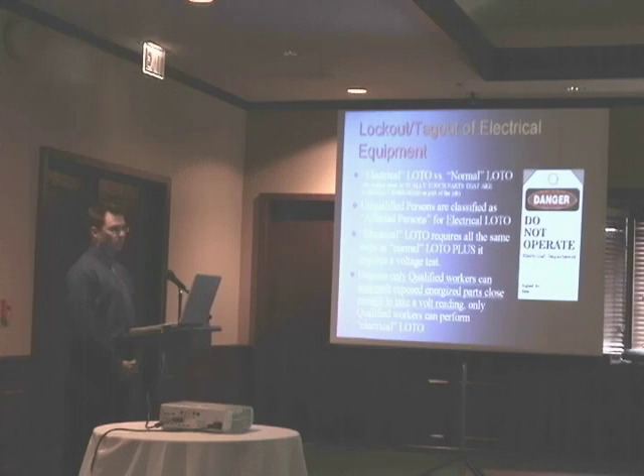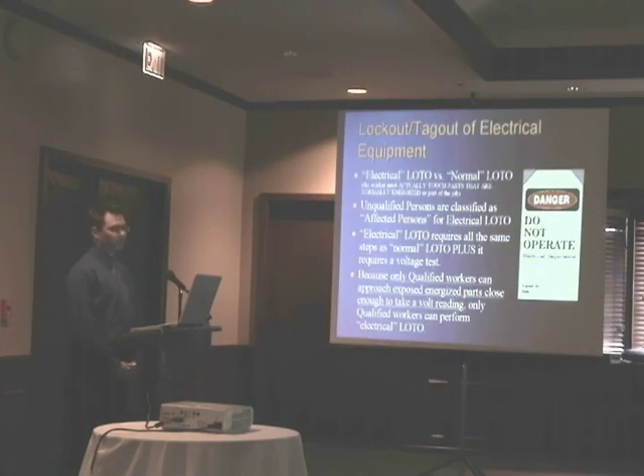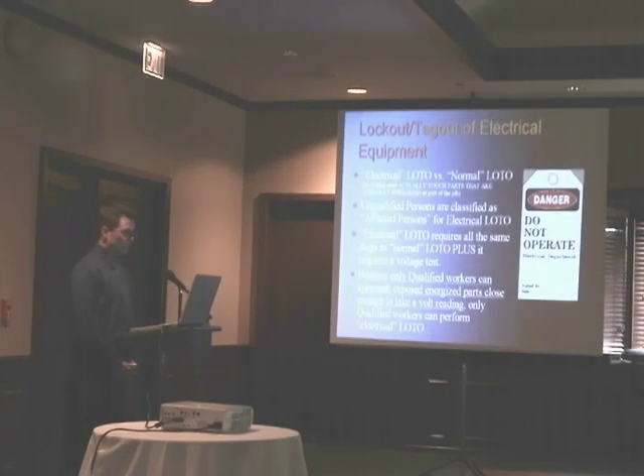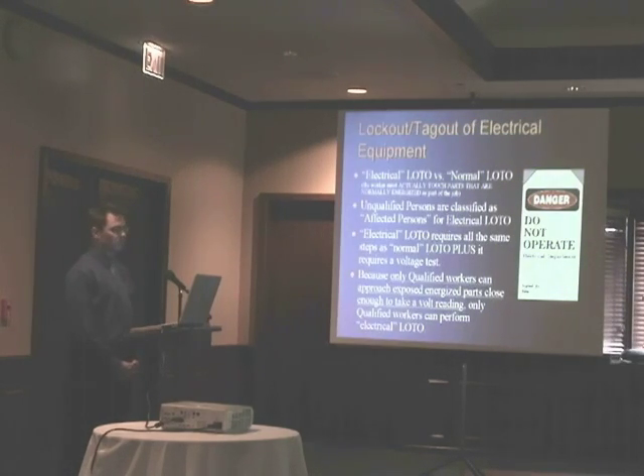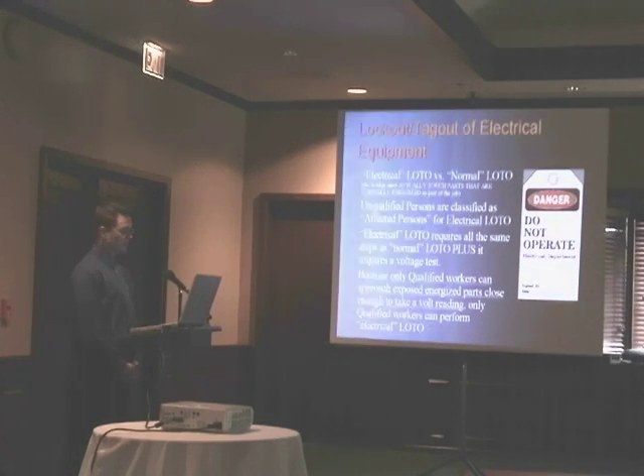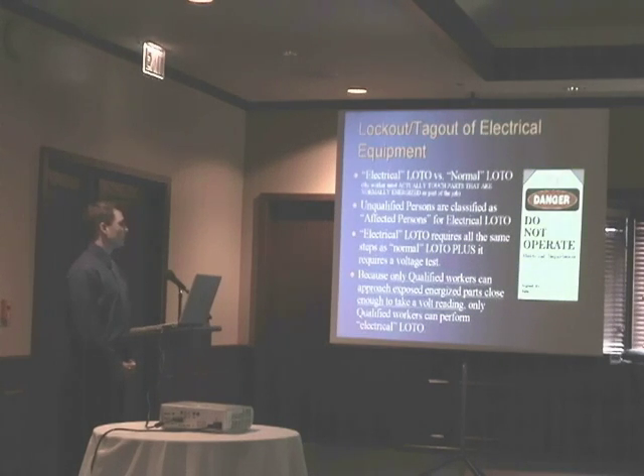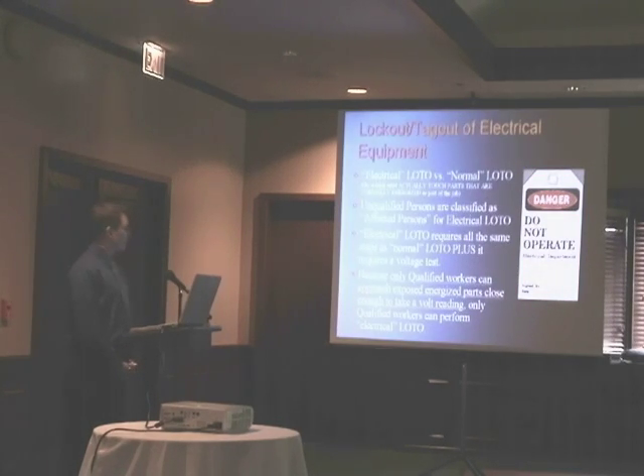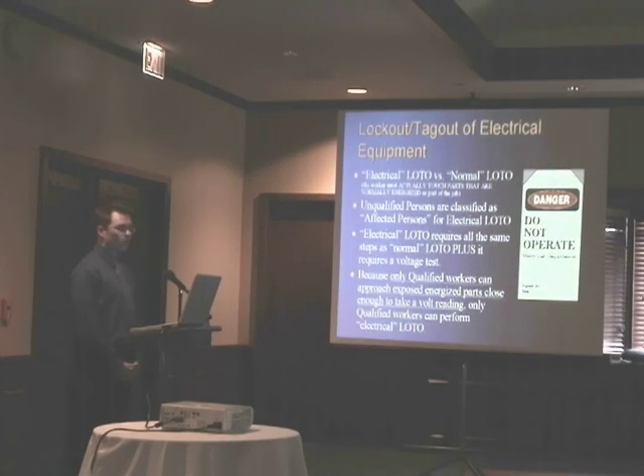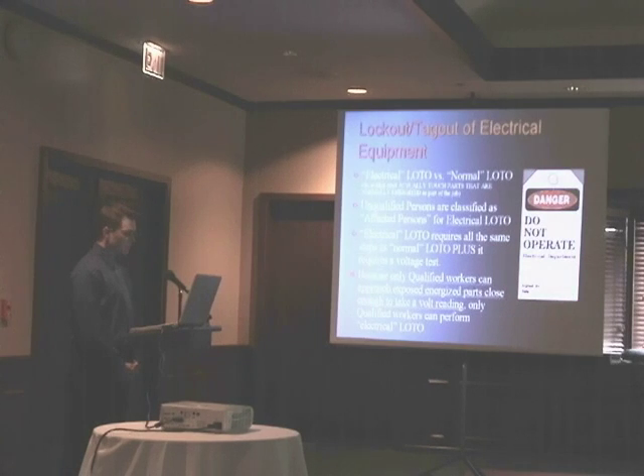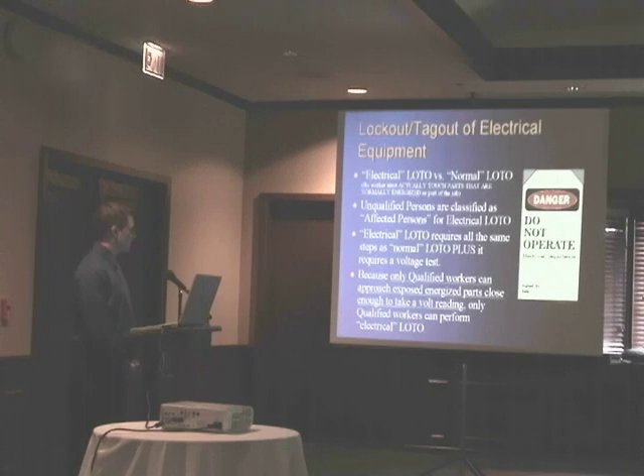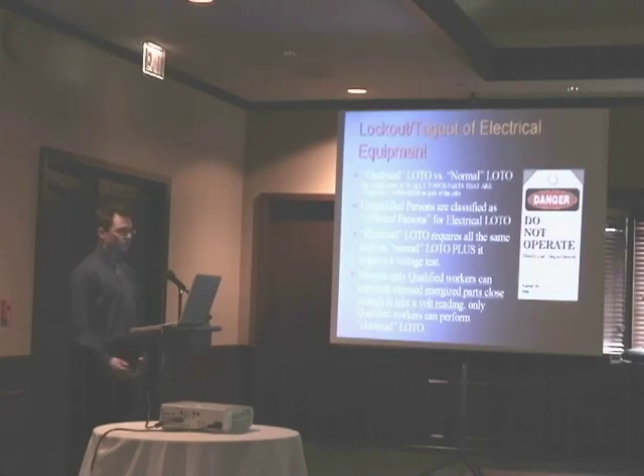The first thing you always want to do before you go to work on any live equipment is to make it not live, and lock out and tag out that equipment. Let's go through what the difference is between electrical lockout tagout and normal lockout tagout. An unqualified person is classified as an affected person for electrical lockout tagout. Electrical lockout tagout requires all the same steps as normal lockout tagout, plus it requires a voltage test. Because only qualified workers can approach exposed energized parts close enough to take a volt reading, only qualified workers can perform electrical lockout tagout.